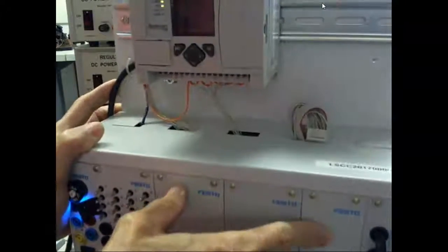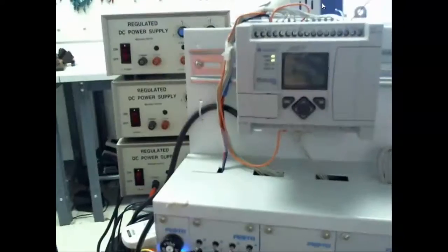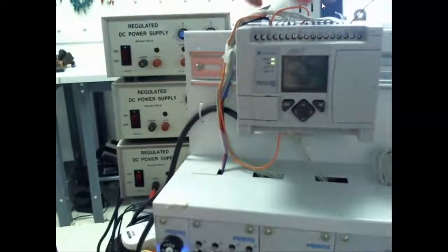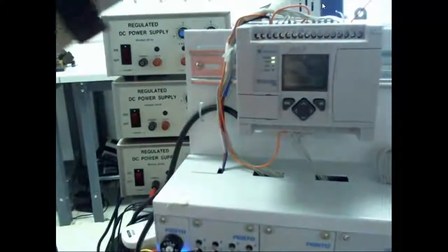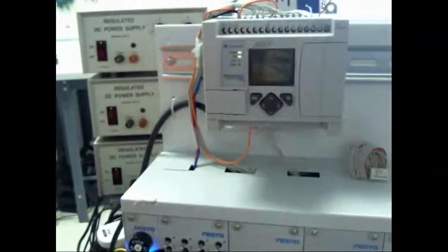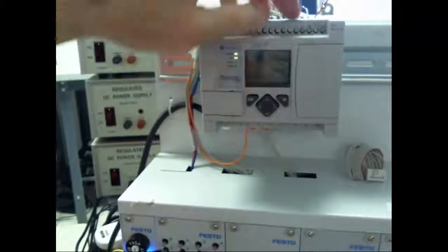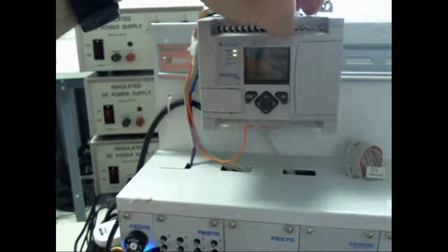Something that this PLC doesn't have that most of your PLCs have now is that the terminal board is actually removable. So the only problem we have with this guy is if the PLC went bad, I'd have to totally rewire it. When I bring one of the 1214s over here, Siemens, and also the newer Allen Bradleys, the terminal board is actually removable.